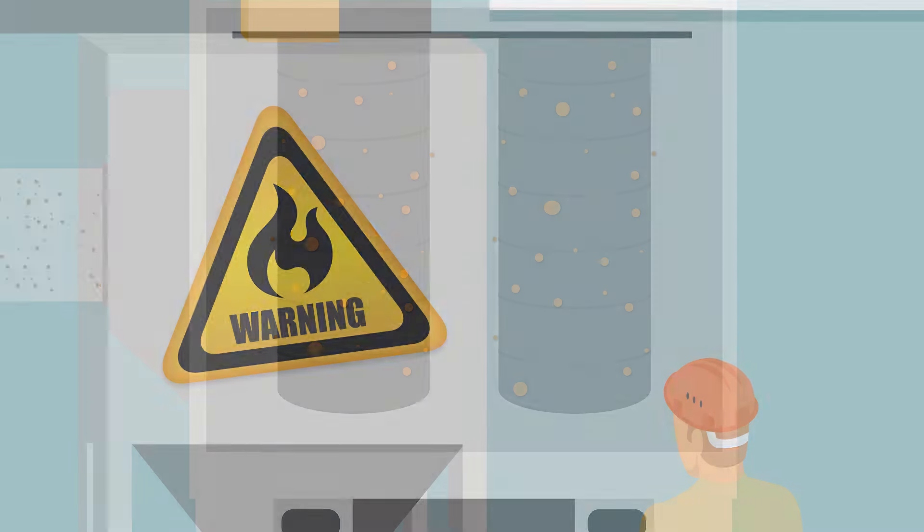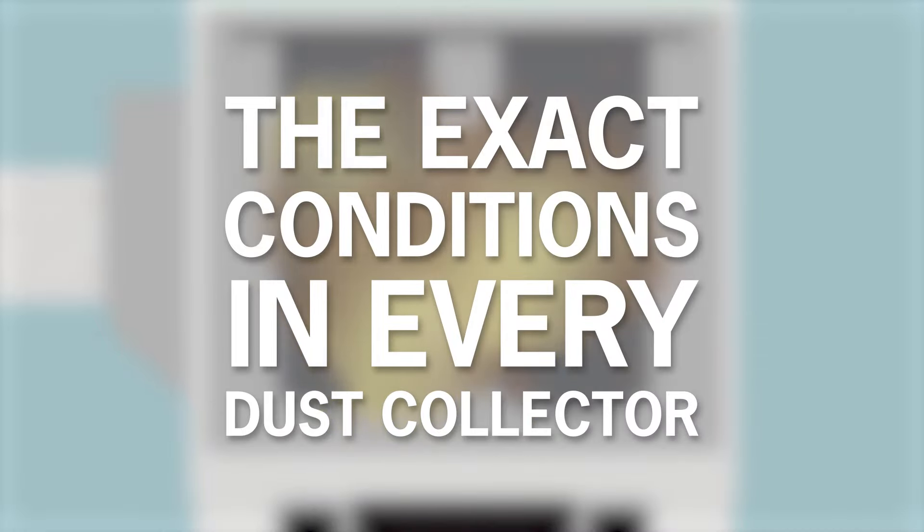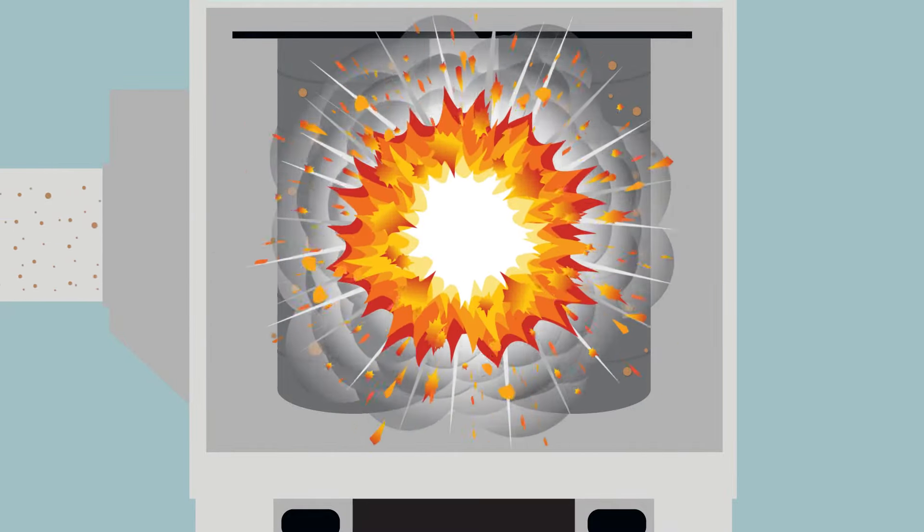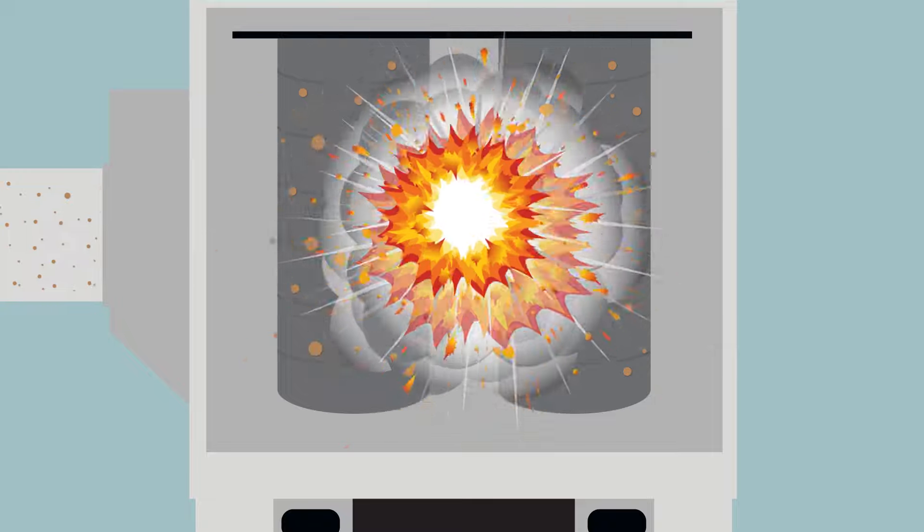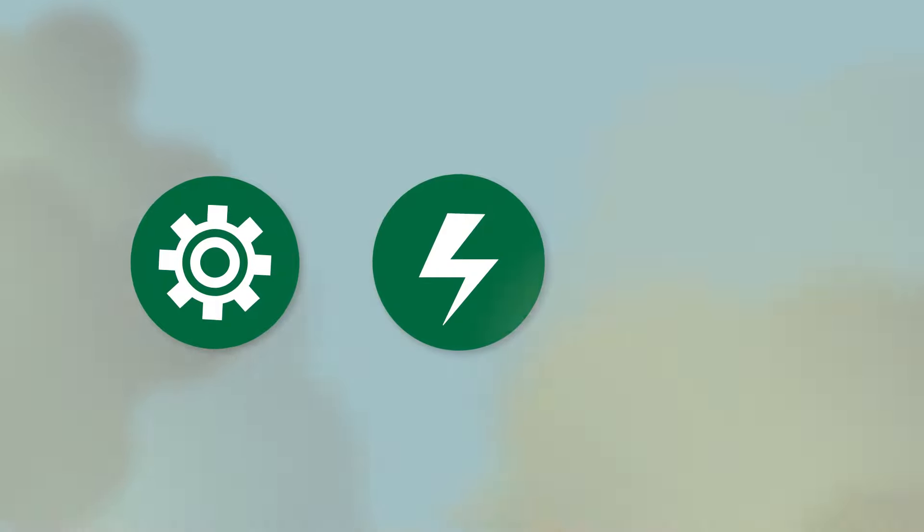Explosions become more likely when a suspended cloud of combustible dust is present in high concentration in an enclosed vessel. These are the exact conditions you'll find in every dust collector. If a fan draws in a spark, that dust cloud can ignite and trigger an explosion that sends heat, flames, and dangerous projectiles into the workplace. The source of the spark could be a production process, a static electricity discharge from nearby equipment, or even a cigarette.